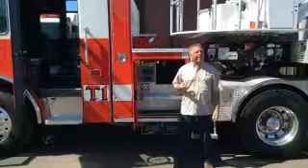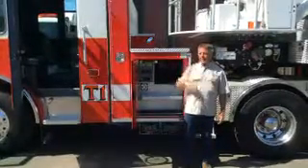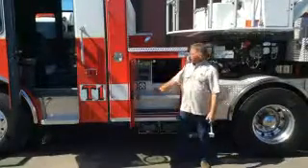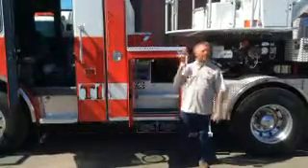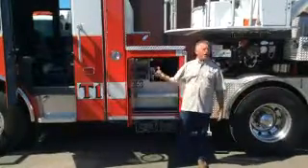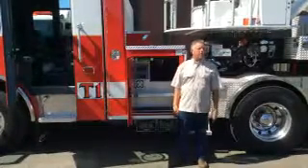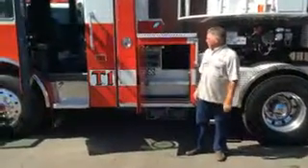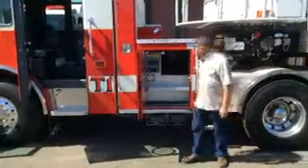If you hit it again, it will tell you the operating temperature of your generator. I tell them, try to keep it below 180, because if it gets above 180, the hoses start to break down. You'll smell them. Okay? If it's flashing at you like that, it means you're trying to pull too much electricity out of the cord reels or wherever you've got something plugged in. So then they can bump up their high idle. The alternator will go to its peak output to assist the generator in what it's got to do. It should turn solid again as long as they're not trying to pull too much. If you leave it alone, it goes right back to the main line. So that's the way that works.